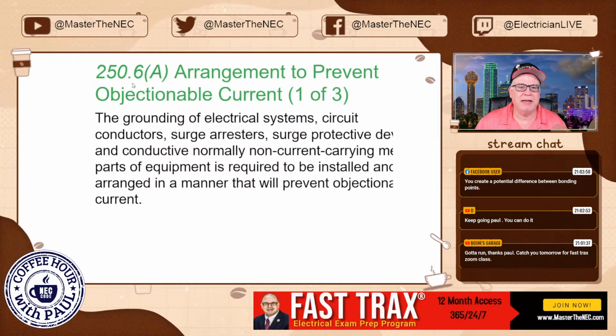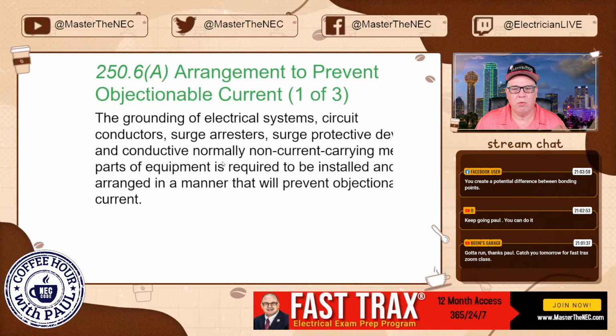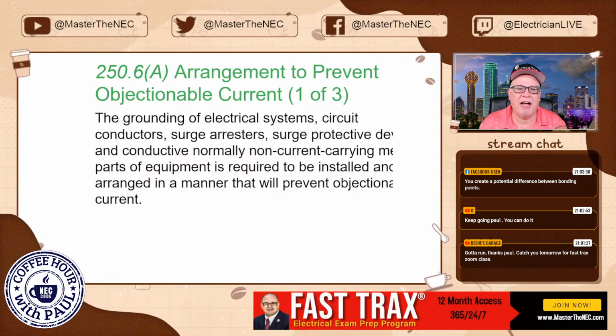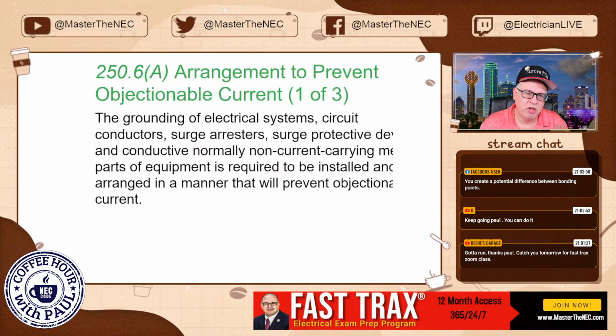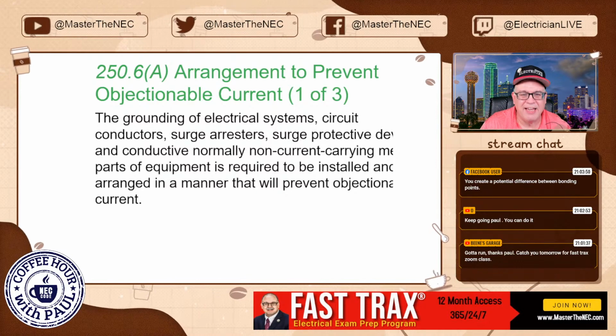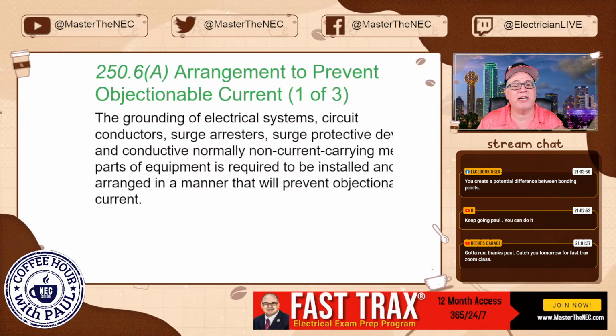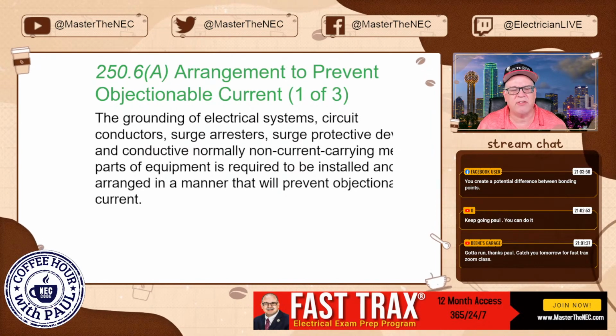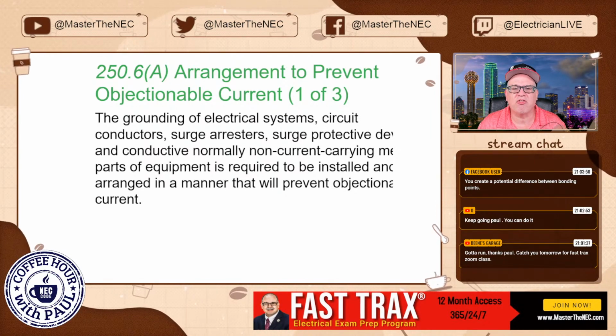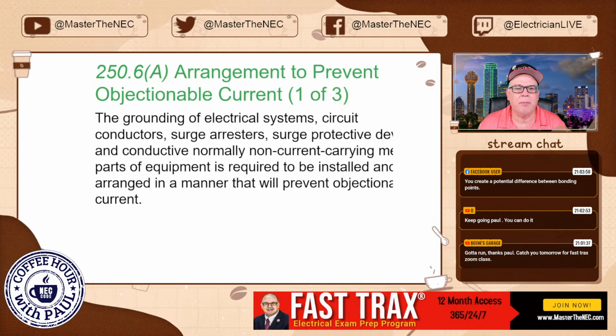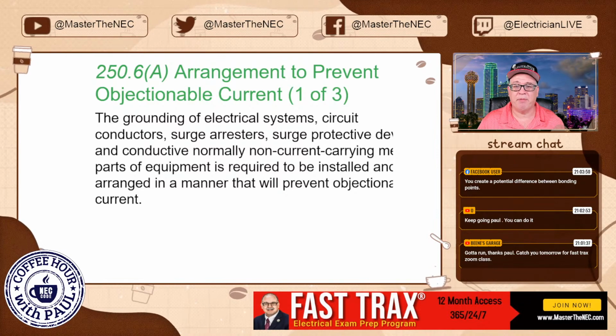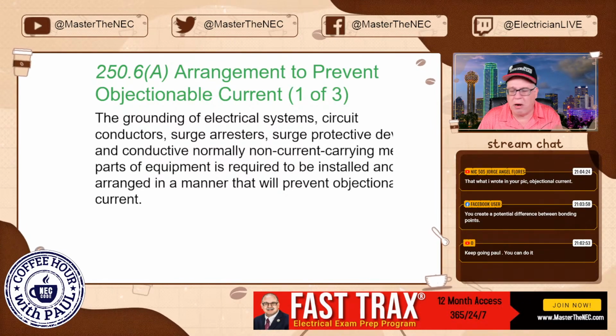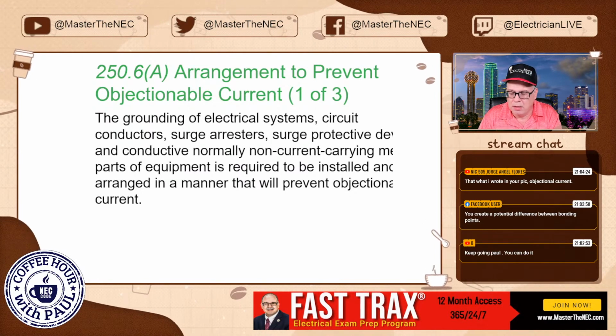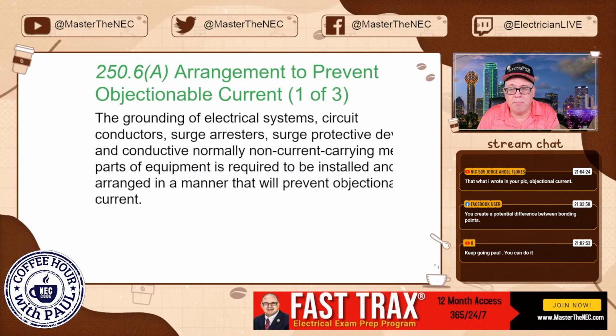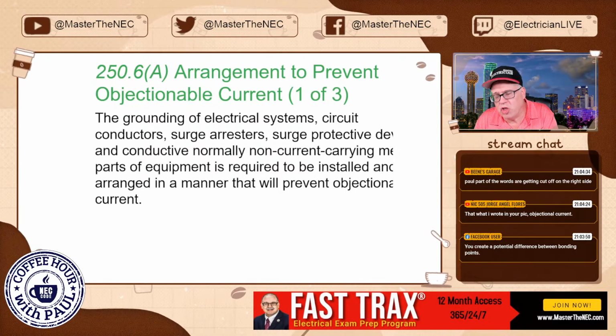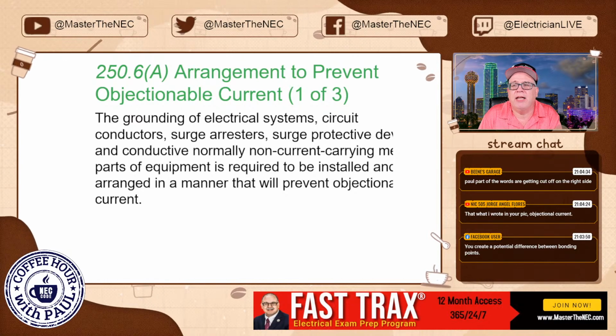250.6(A), arrangement to prevent objectionable current. What do we got to do? 250.6(A) says the grounding of electrical systems, circuit conductors, surge arresters, surge protective devices, and conductive, normally non-current-carrying parts of equipment, that's the metal cabinets, the wireways, all that, is required to be installed and arranged in a manner that will prevent objectionable current. A good example of this is downstream anywhere. You do not want to make a connection of the grounded conductor, or in most of the cases you and I deal with, the neutral conductor. You do not want that making connection in the box or in a cabinet.